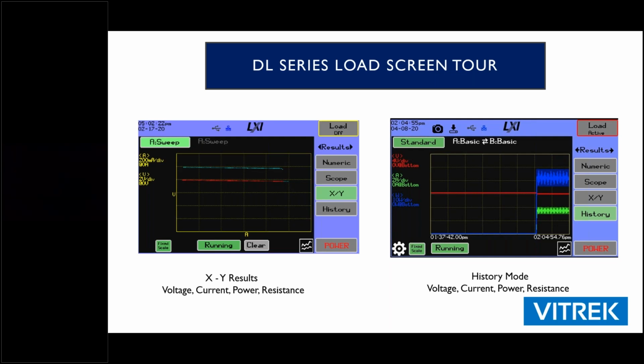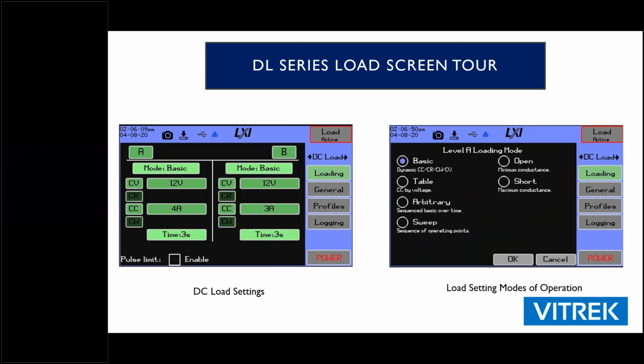So this is the setup screen here on the left. You're going to go in and be able to set your voltages, your maximum currents, and the time associated with it. Here you'd be looking at a test that's going to take you from 4 amps of loading to 3 amps of loading, 3 seconds back and forth, pretty standard.